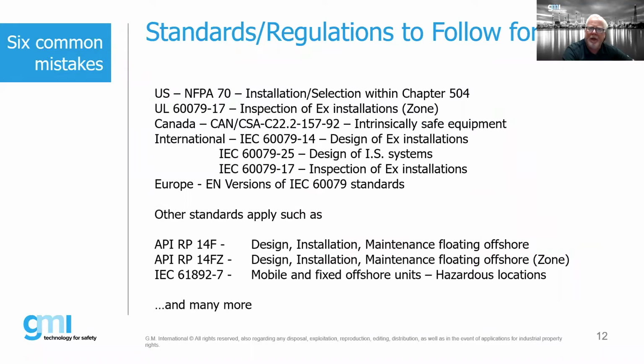Again, in the US, we follow NFPA 70, commonly referred to as the National Electric Code. Article 504 gives us all the details of the requirements for installation and design. We have a new UL standard, which I was part of the committee for, on inspections of EX equipment, which includes inspections of intrinsically safe systems. In Canada, it's the C22.2. On the international side, we have a bunch of different IEC standards that we have to comply with. The main ones for IS fall within the -14 standard, which is the design of EX installations, as well as -25, which is the design of IS systems. There is a significant amount of overlap between the two, but basically, if we follow the requirements of the -14 and the -25, that's the main stuff. The -17 covers inspections, which again include IS.